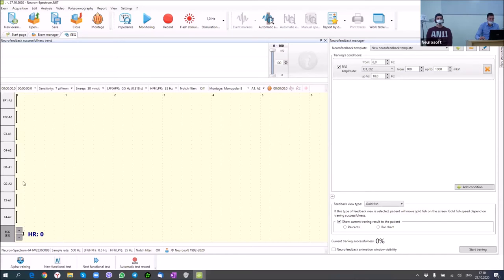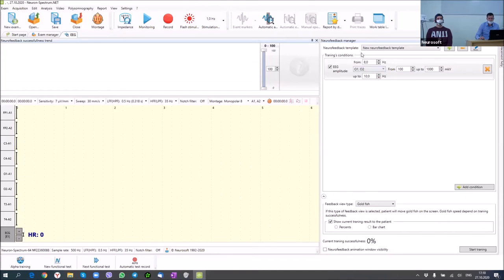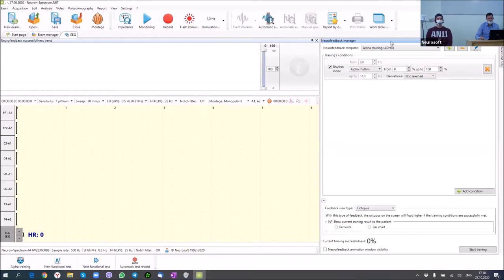We can also see the neurofeedback training success trend and the neurofeedback manager for the doctor, where we can select the neurofeedback template. For example, we can choose alpha training for attention deficit and hyperactivity disorder. We can select a template that contains one or several different conditions. According to these conditions, the software calculates training successfulness and shows feedback to the patient. Let's start training to see how it works.